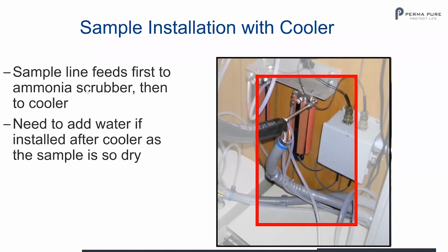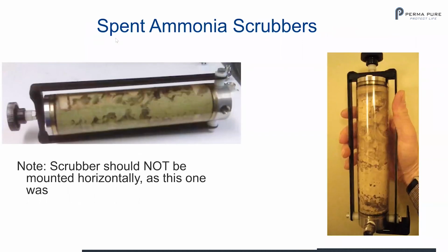And here's a sample installation with the cooler. So what we want to do is remove that ammonia before the cooler. Some people remove it after the cooler to make sure the ammonia doesn't combine with the water and the other components to form acids on the analyzer. It can be done either way. And here's what a spent ammonia scrubber looks like. Note, the scrubber should not be mounted horizontally as this one was.